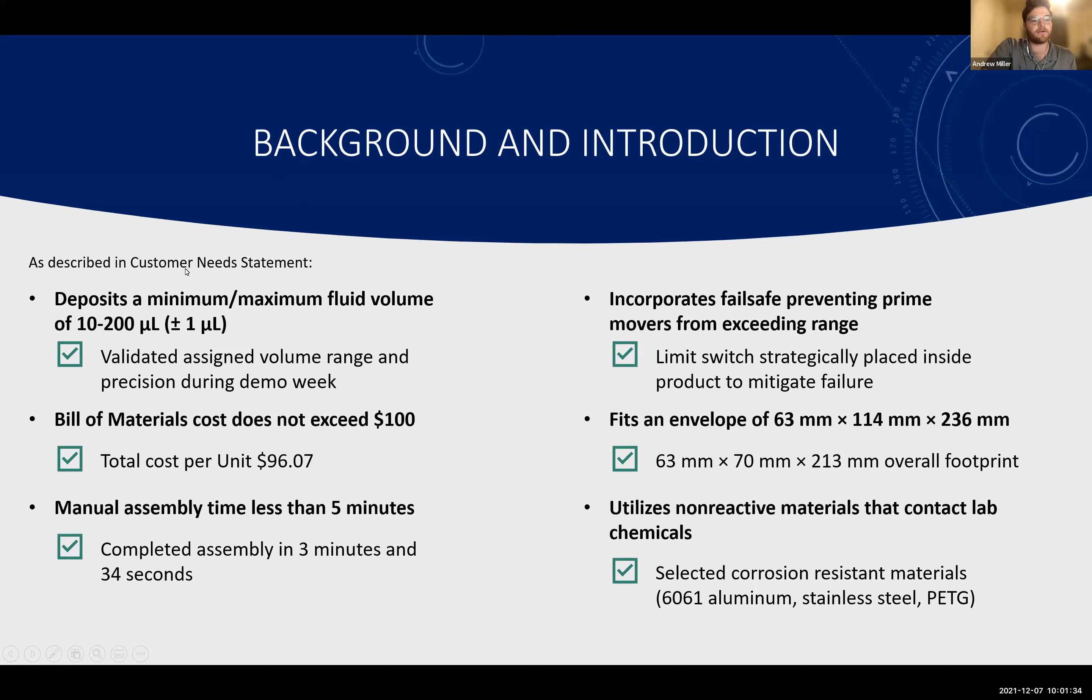A little bit of background and introduction. As described in our customer needs statement, we were tasked with dispensing 10 to 200 microliters with a one microliter precision. This was validated during our testing week and precision was also done during our demo week.